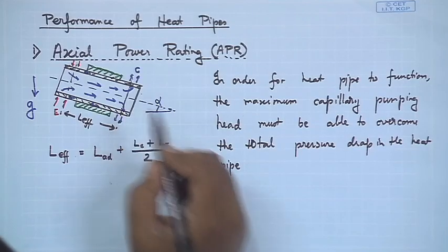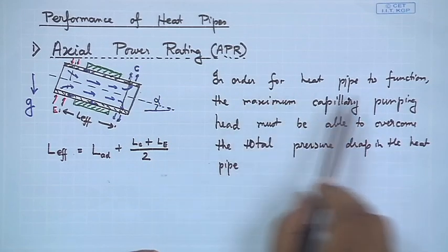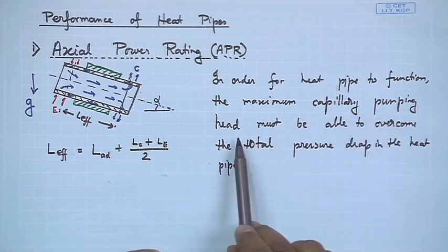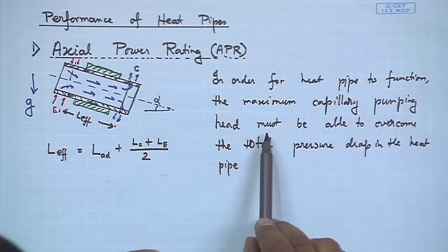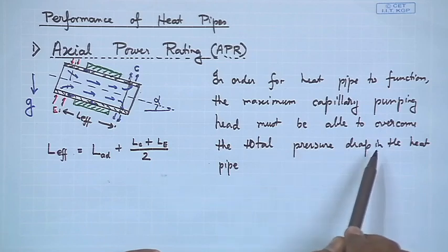Welcome. We will continue our discussion on heat pipes. Last time we started to derive an expression for the maximum amount of heat that can be pumped by a heat pipe from its evaporator to the condenser end, which is known as the axial power rating. For the heat pipe to function, the maximum capillary pumping head provided by the wick must overcome the total pressure drop of the fluid as it flows through the heat pipe.